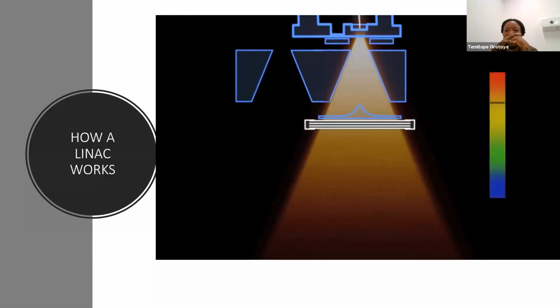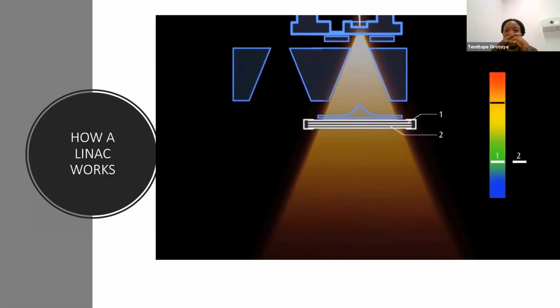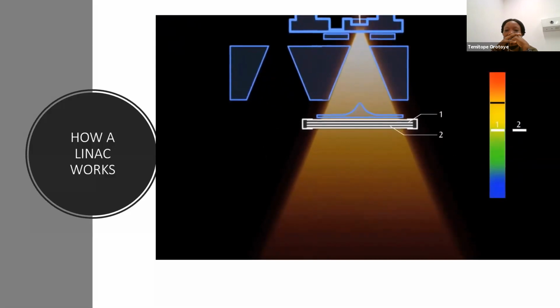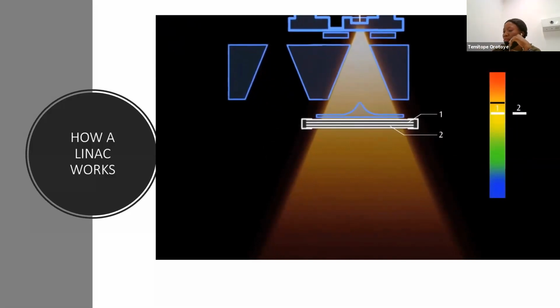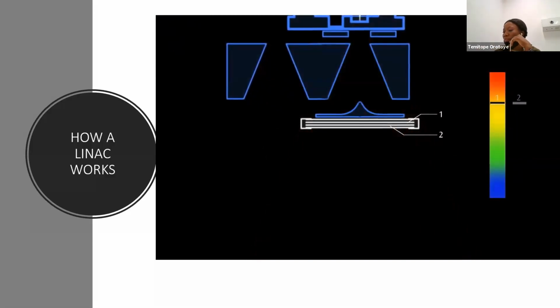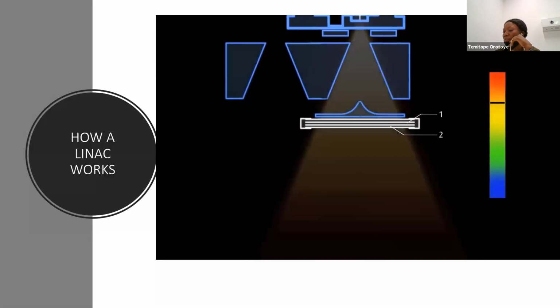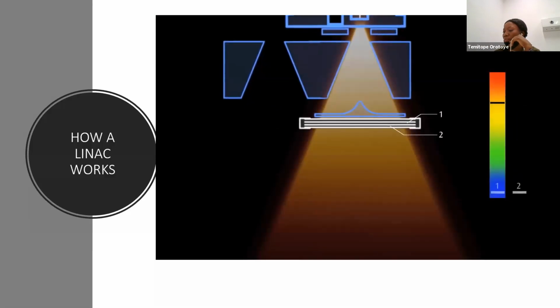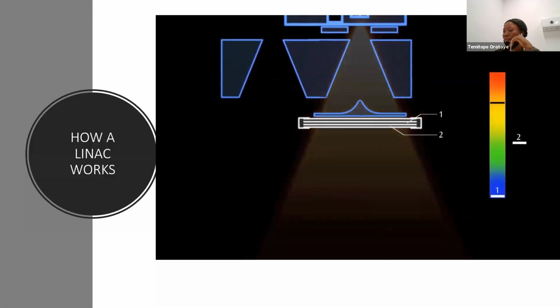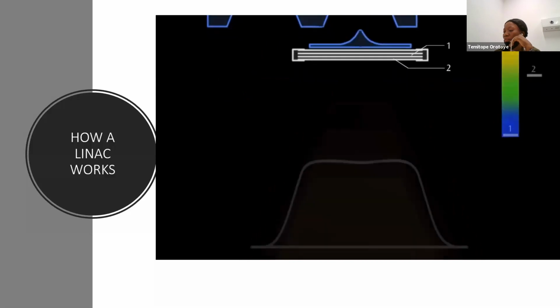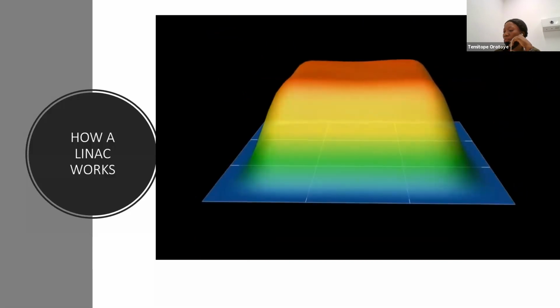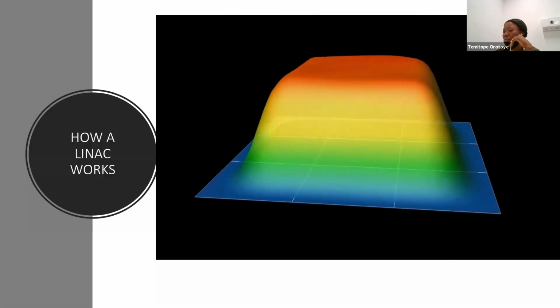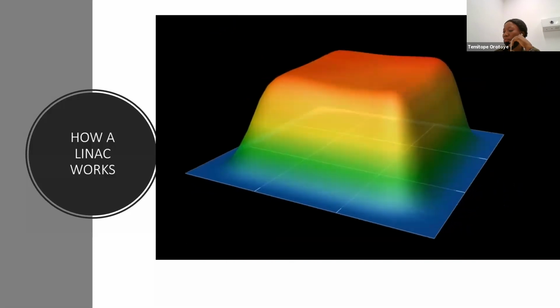The dose delivered to the patient is measured and controlled simultaneously in two independent ionization chambers. One chamber is the primary dosimeter. It measures the radiation and terminates the beam when the required dose has been delivered. The secondary ion chamber acts as a backup and will stop the irradiation if the primary chamber fails. The treatment machine must replicate the beams modeled within the planning system. This is critical to the accuracy of treatment delivery.